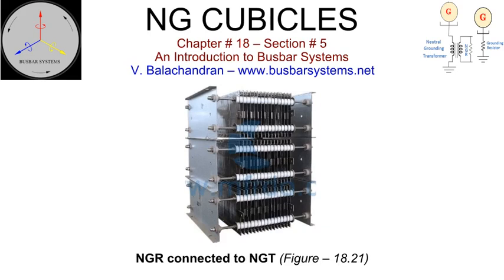Neutral grounding resistors for high impedance neutral grounding. The resistance banks can be mounted one on top of the other without the insulators in between. The entire assembly of the banks has to be mounted on standoff insulators. The body of the resistance bank shall not be earthed. Each bank of the neutral grounding resistor is rated for 1.1 kV. Each bank comprises several punched stainless steel elements connected in series. This is achieved by installing conducting washers and insulating mica washers alternately. The entire grid assembly is supported on a filament wound FRP tube running over a stainless steel rod. The rods are connected to the end plates with a low-voltage insulator assembly. The pattern of punching defines the resistance of each element. It is preferable to have taps at ±10% and 20% of the total resistance of the assembled bank.